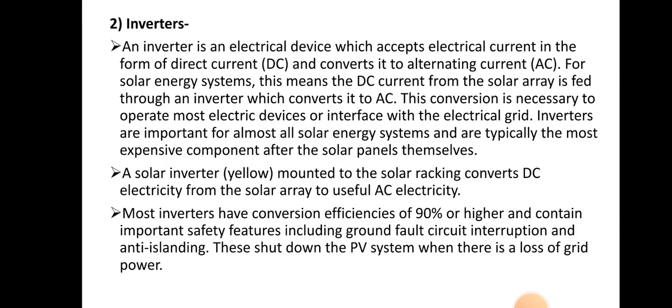After the solar panel, the inverter is the most expensive component in the solar photovoltaic system. The solar inverter, mounted to the solar racking, converts DC electricity from the solar array to useful AC electricity. Most inverters have a conversion efficiency of 90% or higher and contain important safety features including the ground fault circuit interruption and anti-islanding, which shut down the PV system when there is a loss of grid power. In simple terms, the inverter converts DC current from the solar panel to AC current for home appliance circuits.